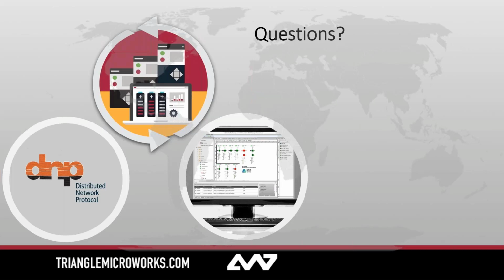And then to answer the first part of that question, I mentioned a few times throughout the webinar, very briefly, we have an application called SCADA Data Gateway. That is our protocol mapping. It's a translator, a data concentrator. These are deployed into substations, right? So this is not a test tool. This is an actual deployable application. Granted, you could use it as a test tool if that's what you needed, just for something in your lab, but it is robust enough to be put into a substation.